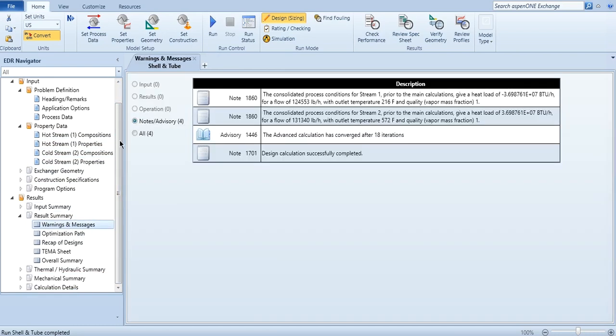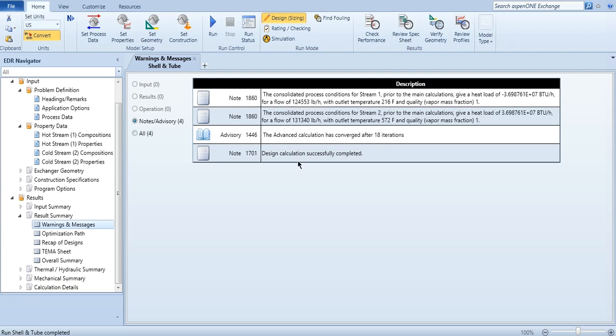And then once after clicking on this run, you will get the warning messages. And there is no warning involved, there is just an advisory on notes available, that the consolidated process condition from stream one prior to calculation will give a heat load of this, mass flow rate of this, and then outlet temperature of this, and same for the second stream. The advanced calculation has converged after 18 iterations, and design calculations successfully completed. Once you get this type of information, it means that the design has been okay. If you get any information in input or if you get any warning, you need to first resolve that warning before getting an acceptable design.